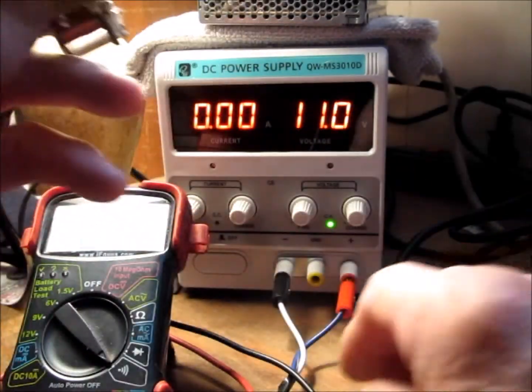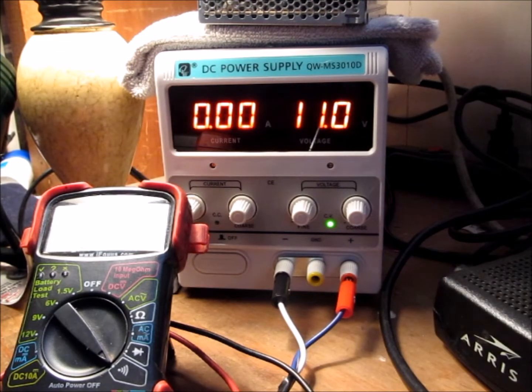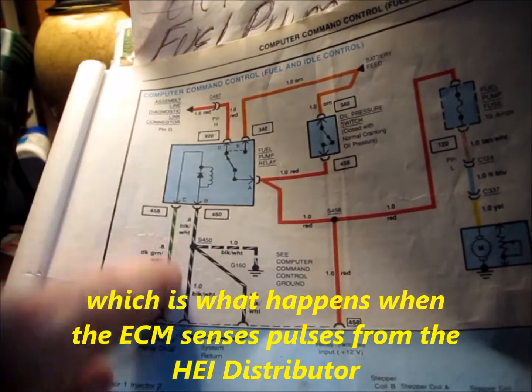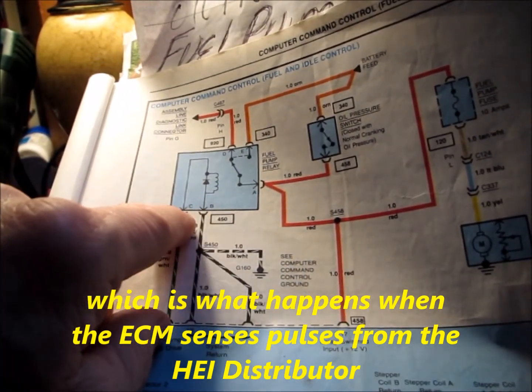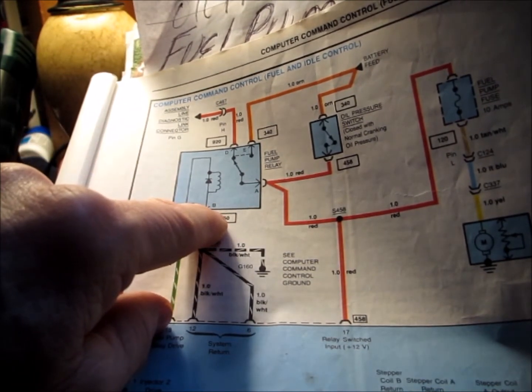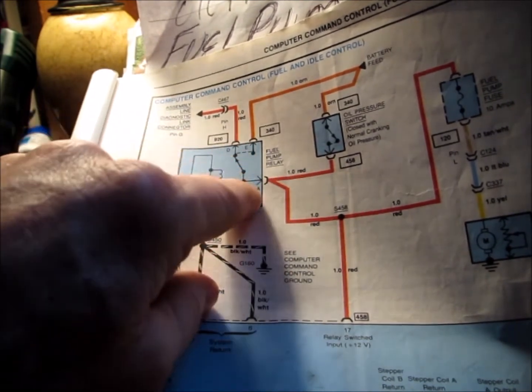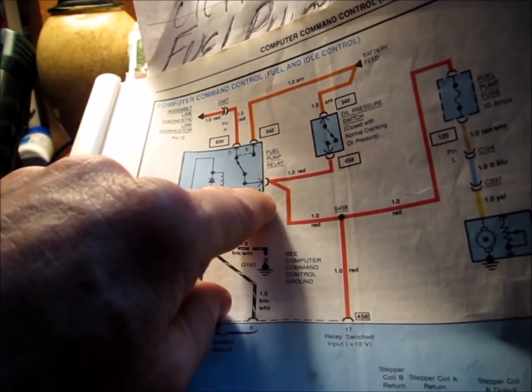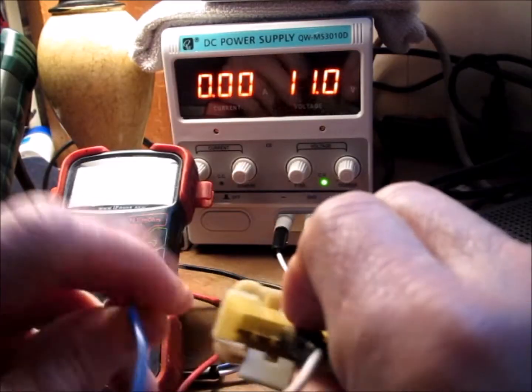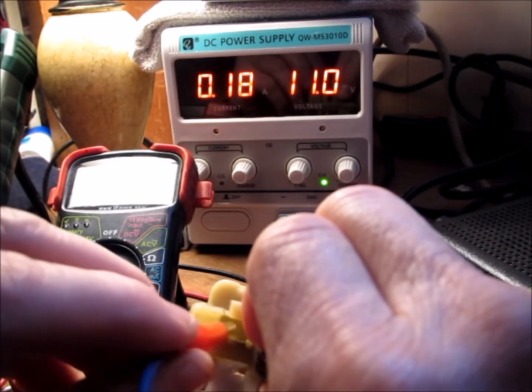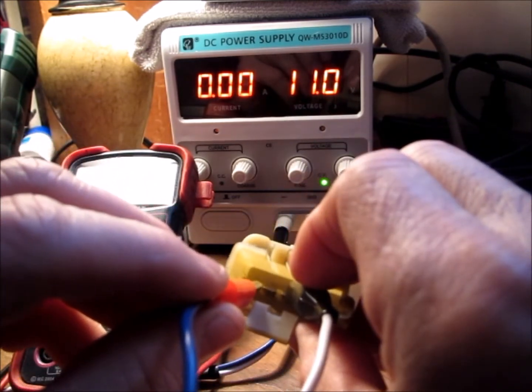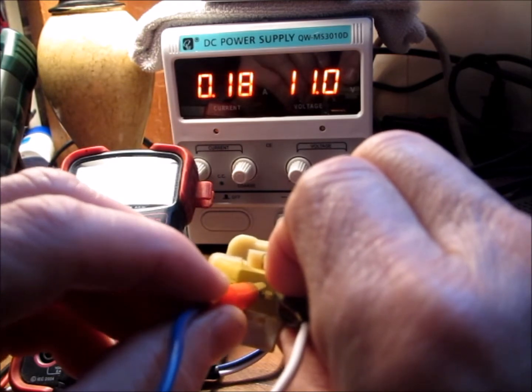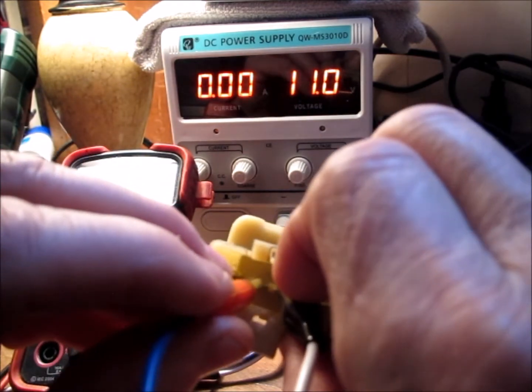If you energize the coil by putting current to B and C, you should hear it click. You should hear the relay click, and then you should have continuity between A and E. I don't know if you can hear that or not, but it's clicking.